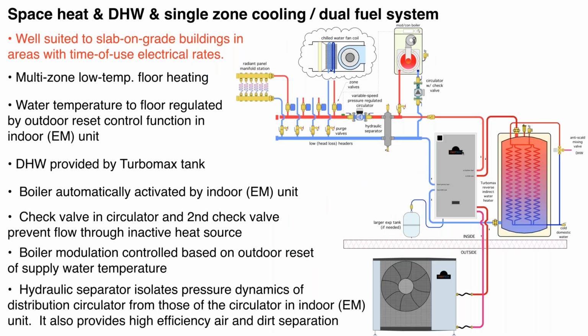Now, another option with this system is a configuration on the indoor unit control capability to operate an auxiliary heat source. It's referred to as a dual fuel system, where I'm showing here a ModCon boiler that could operate on natural gas if the house happens to have natural gas service, and it might or it might not. It could operate on propane. It would also be possible to tie in a conventional boiler, for example, operating on fuel oil.